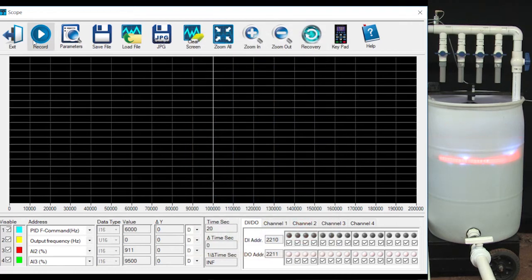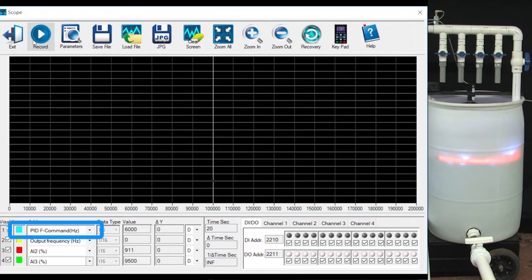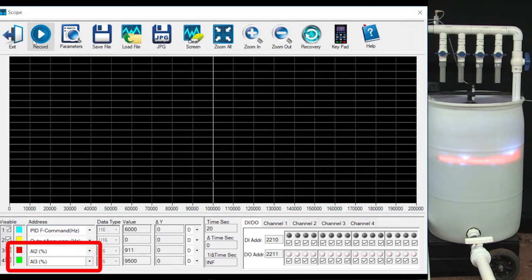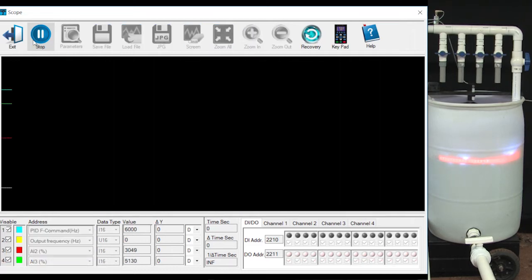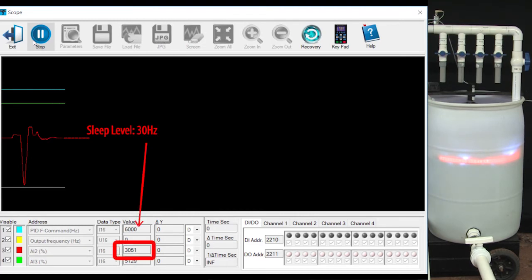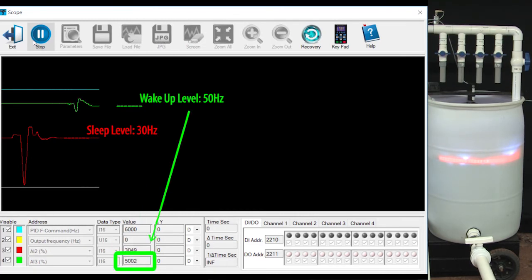I've already set up the GSoft2 scope function with the PID generator frequency command in blue and the actual output frequency in yellow. These are just analog potentiometers I connected to analog inputs 2 and 3 so we can use them as cursors. Let's adjust those potentiometers to remind us that the sleep level is at 30 Hz and the wake up level is at 50 Hz.